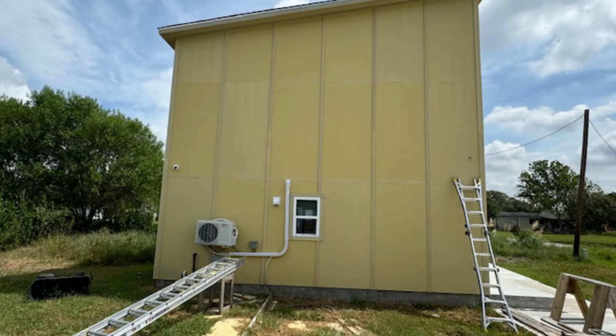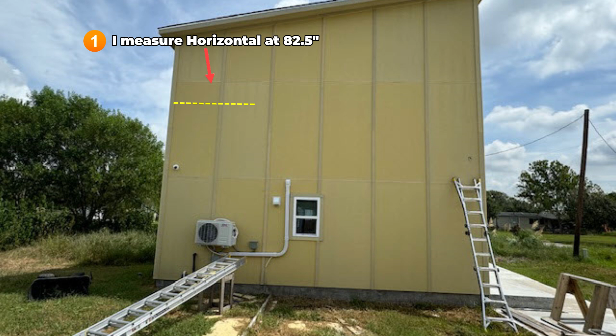First things first, I always start with a clear site plan and diagram. This helps me visualize exactly where everything will go, both inside and outside. It also ensures that measurements are precise before we start installing any equipment. Step 1. Measure the horizontal distance. Measure the horizontal distance from the reference point on the wall. In this case, the horizontal measurement is 82.5 inches. Mark the position on the wall clearly to ensure proper alignment for the next steps.